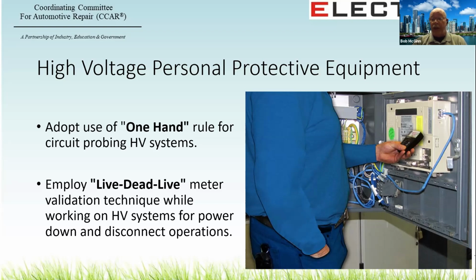Meters should be tested in the same range and mode for live dead live and voltage absence tests, which means you may want to switch the meter to a static range instead of letting it auto range. If you have something as old as mine, it will drive you crazy waiting for it to keep up.